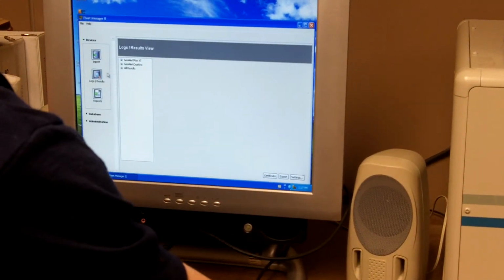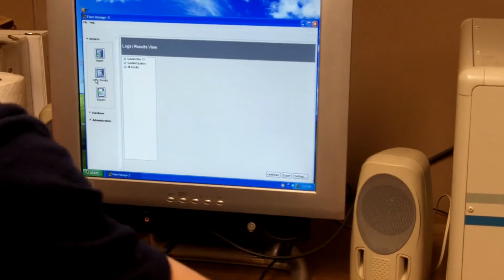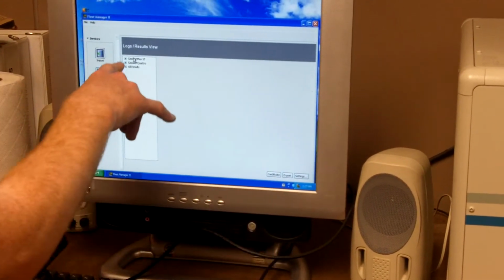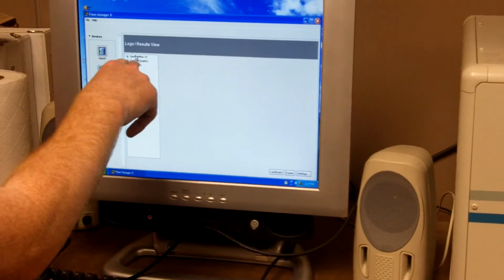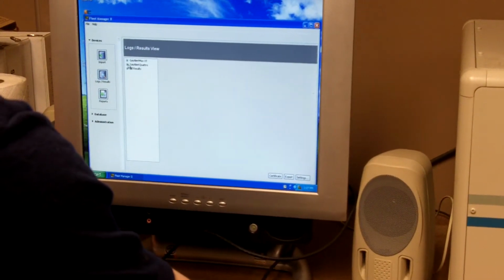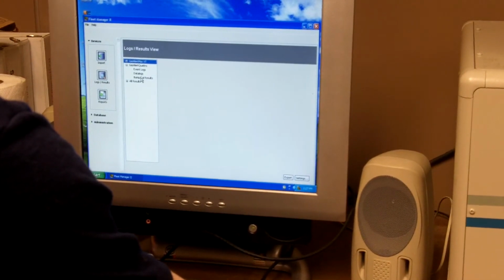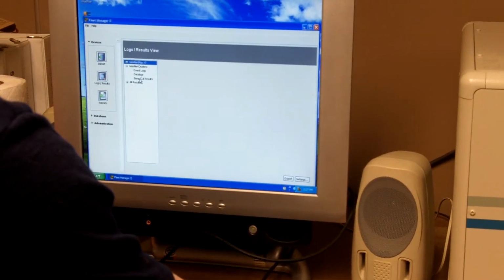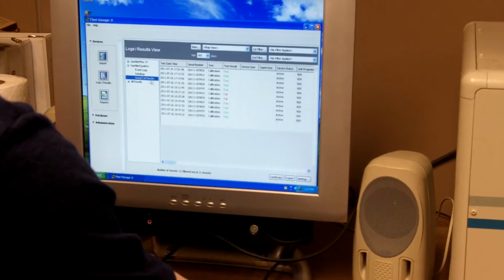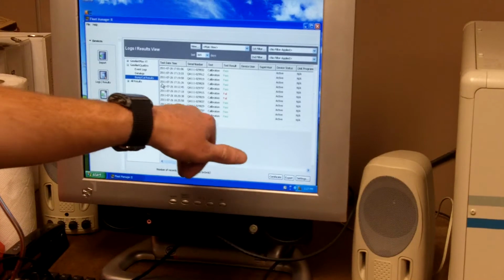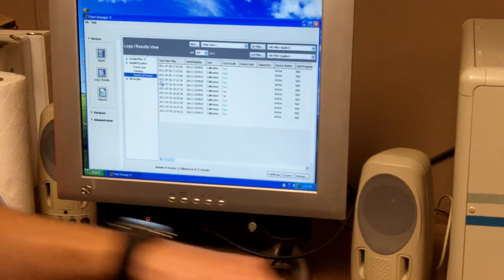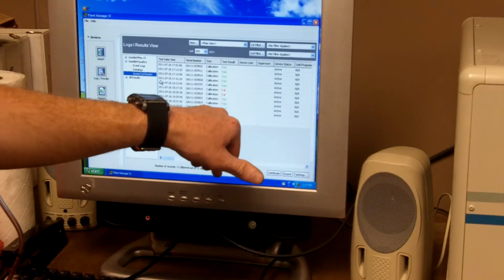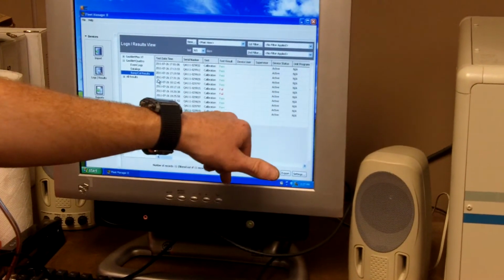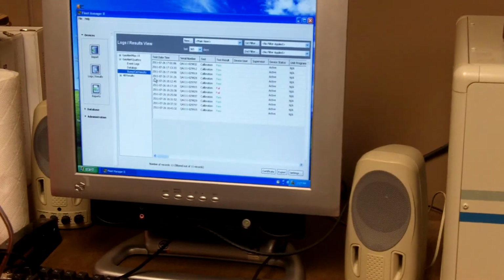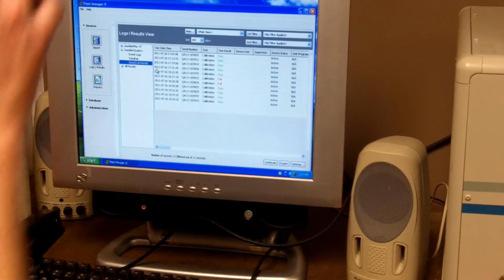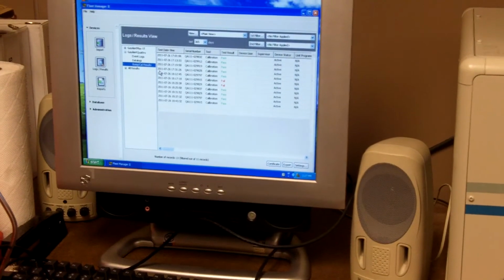And I could check that. So for the last one, I'm going to hit to be able to check what I have, log/results. And then it has it broken down to the gas alert Max XT2 or the gas alert Quattro. So if I'm looking at a Quattro, I'm going to open that up, and then at the very bottom of that, it says bump calibration results. So I click that, and it brings up when it was last checked, the date, the actual serial number, so each gas detector is different, and then the calibration, or if it's a bump check, and then it'll say if it's passed or failed, and if it's active or not. So you'll do all these checks, you'll log it in there, and you should be ready to go.